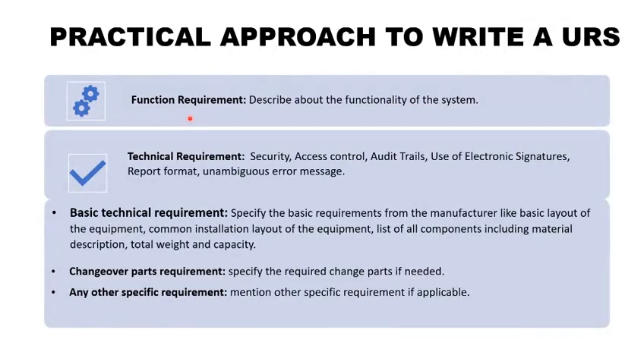Next is functional requirements — describe the functionality of the system, for example sequence and method preparation, sequence execution, integration of data, and reporting of results. There are many technical functionalities required for a computerized system, so it is recommended to address all requirements based on the system complexity and regulatory requirements.